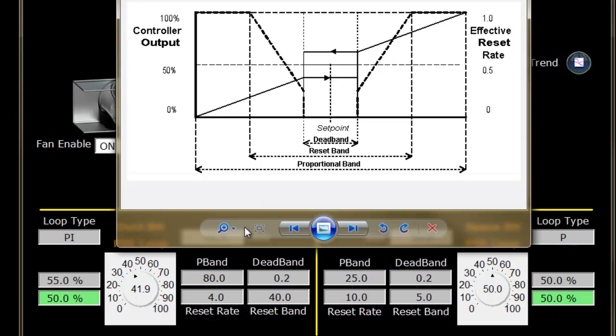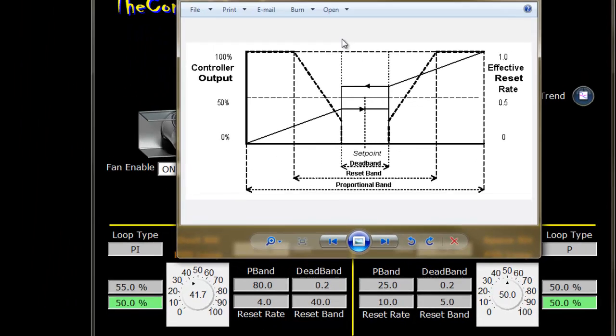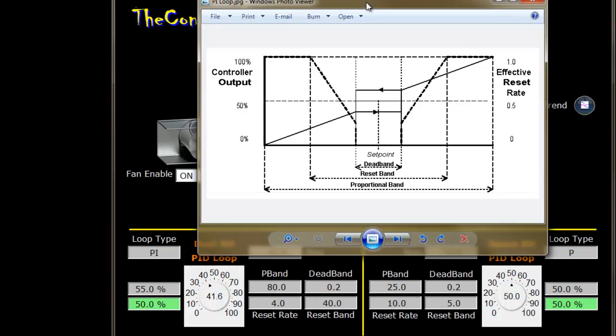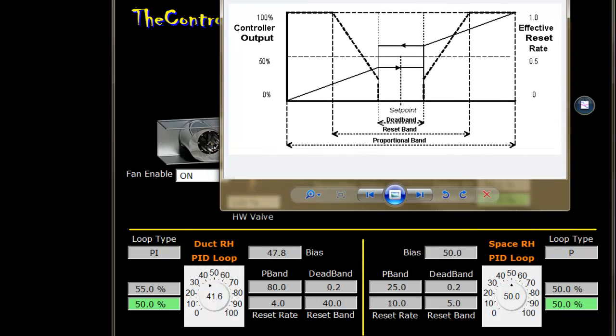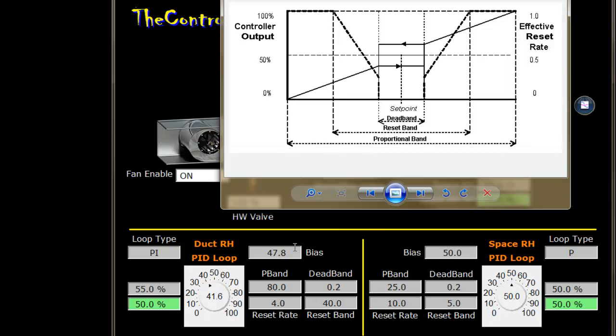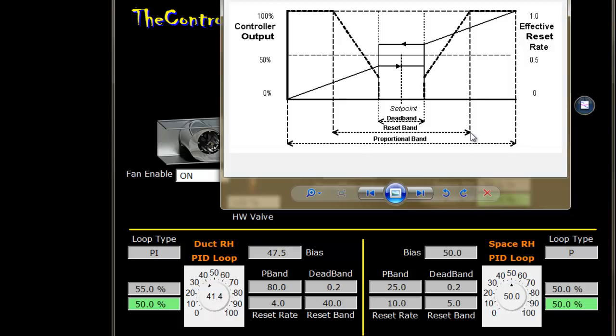The reset band says as you get to its limits, I want you to continue to give it more speed—utilize the full rate. The reset rate of 4 represents 4% of the bias. Since we're using percentages as humidity, this means literally after one minute, if we are outside this reset band—which is 20% away from set point—we'll utilize the full reset rate of 4.